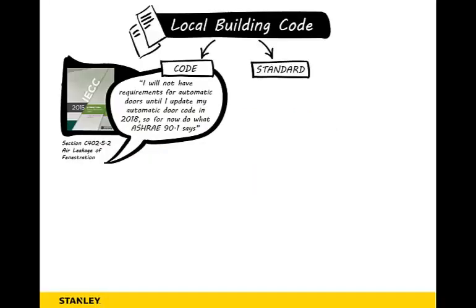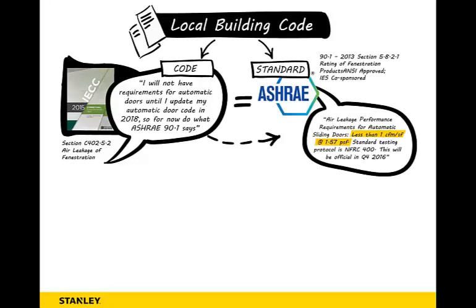The go-to code is the International Energy Conservation Code. Right now, the IECC is saying it doesn't have requirements for automatic doors until it updates its automatic door code in 2018. So for now, do what ASHRAE 90.1 says. ASHRAE 90.1 says air leakage performance requirements for automatic sliding doors shall be less than 1 cubic feet per minute per square foot at 1.57 PSF.